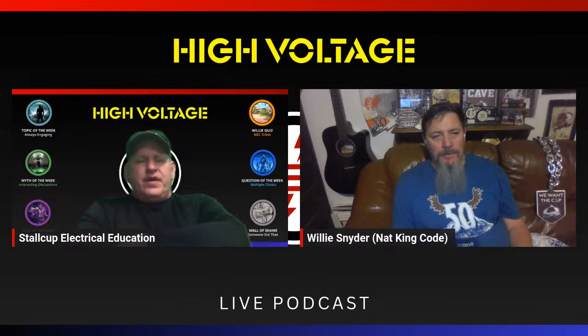And one of the things I like to point out when you're looking at stuff like that, you listen to me do it, it sounds easy. And the reason it is easy, you just have to remember what it is you're doing. If it's a tap, remember these rules of thumb. Anything 10 foot or less, divide by 10. Everything else, take it a third. And if you've got a transformer in the tap, that the tap's not over 25 foot for the primary plus secondary, the primary is a third, and then on the secondary it's a third, but you've got to get the ratio of the transformer. And if it's not a tap, then you just do a normal calculation on the secondary side based on the kVA of the transformer and the voltage, and you've got it sized.